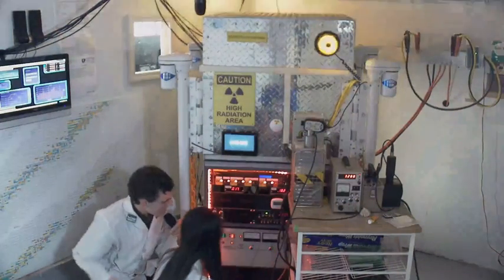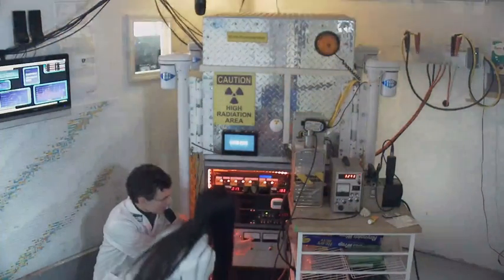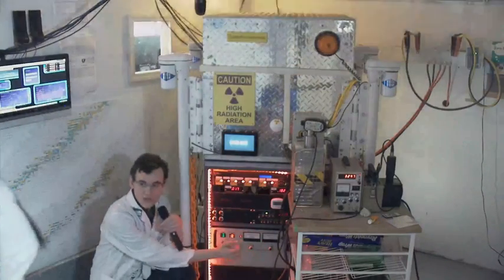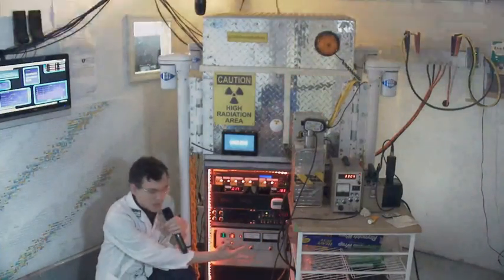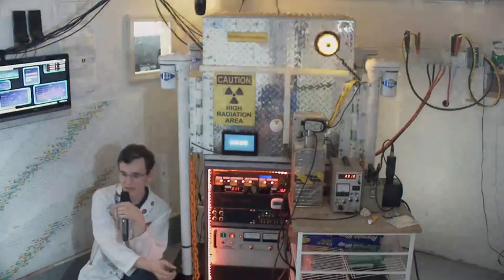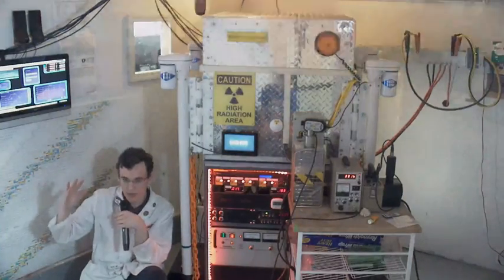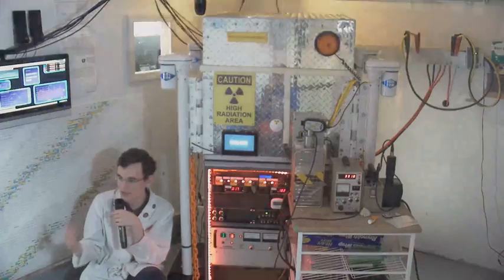So we're at 50, and our current's still at 5 milliamps, and our voltage is still at 30,000 volts. But all of a sudden we've got no change. It's doing the exact same thing. We're letting it give more voltage, but it's not able to put more voltage in. Why is that?